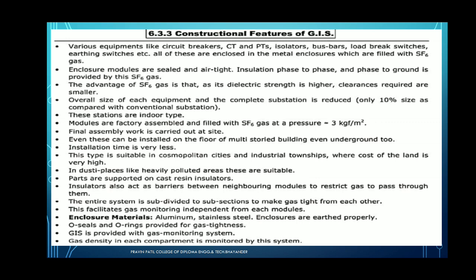The advantage of SF6 gas is that it has high dielectric strength as compared to the insulation of other conventional substations. Clearance required is small. Overall size of each equipment and the complete substation is reduced, here about 10% size as compared to the conventional substation. These substations are indoor types. Modules are factory assembled and filled with the SF6 gas at the pressure of 3 kgf per centimeter square. Final assembly work is carried out at the site.